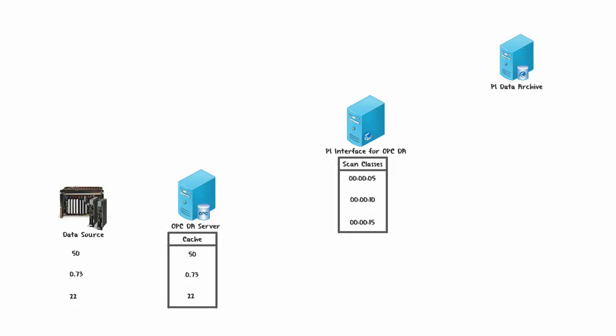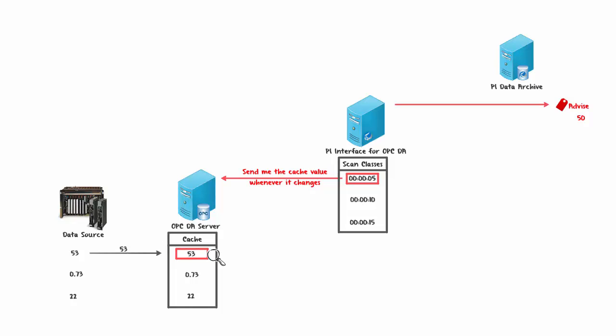For the first Scan Class, if the PI Interface for OPC DA finds an Advise Point, it makes a request to the OPC Server to send it the Cache Value whenever the Cache Value changes — kind of like signing up for updates. So the first value of 50 gets sent to the Advise Point. After an arbitrary amount of time, if the Data Source value is updated, that updates the Cache Value, and this new value gets sent to the PI Interface for OPC DA, which then sends it to the Advise Point.